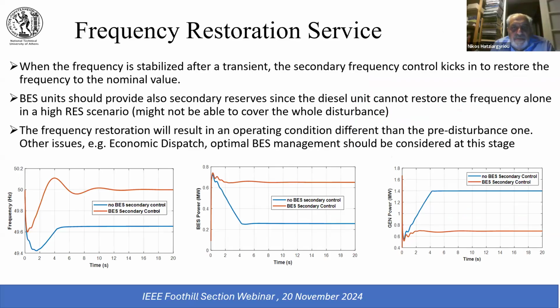Also in secondary frequency control, when the frequency is stabilized after a transient, the secondary frequency control starts to bring frequency to the nominal value. And here the issue is if you will allow the battery to provide secondary reserves, especially when the diesel units cannot restore the frequency in a high renewable scenario, because they don't have the capacity to do so.